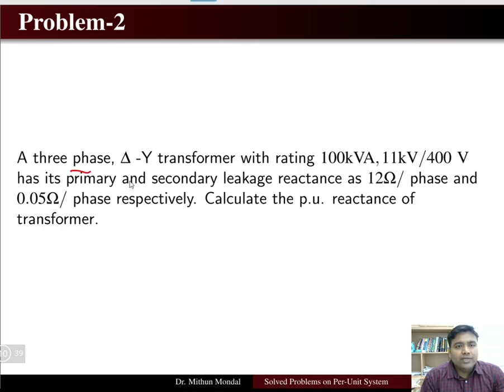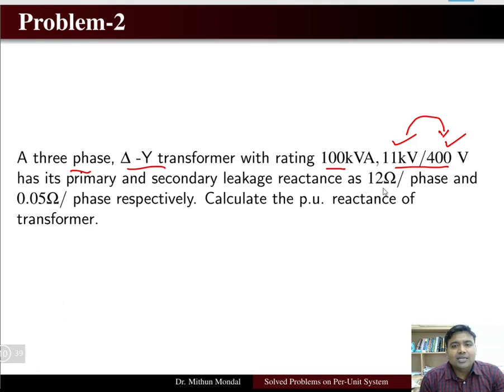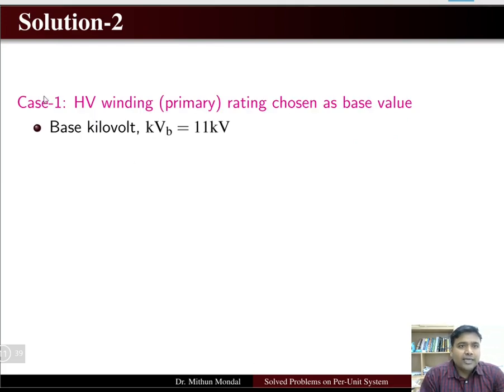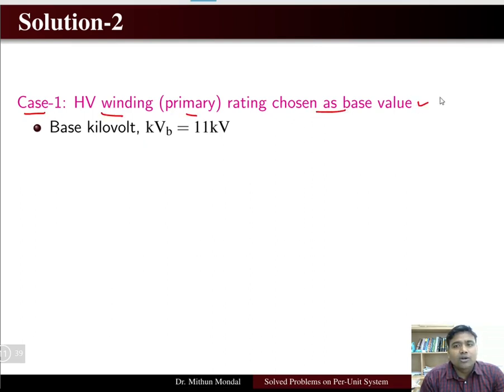Problem number two: a three-phase delta-star transformer rated 100 kVA, 11 kV / 400 V. Its primary and secondary leakage reactances are 12 ohm per phase and 0.05 ohm per phase respectively. Calculate the per unit reactance of the transformer. We will take two cases: Case 1 uses the high voltage winding rating as the base value, and Case 2 uses the low voltage winding rating as the base value.